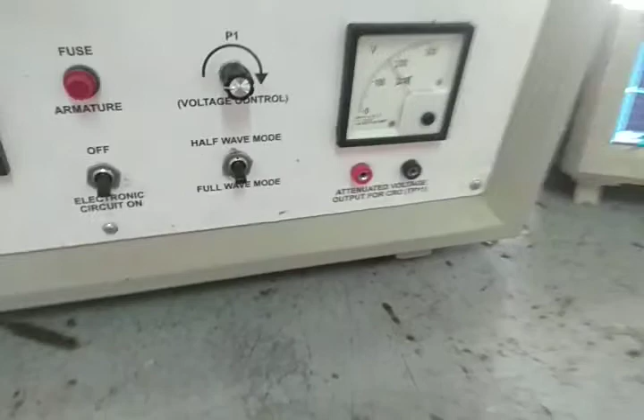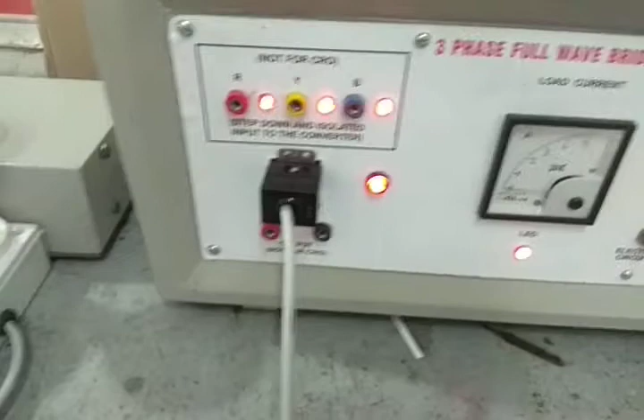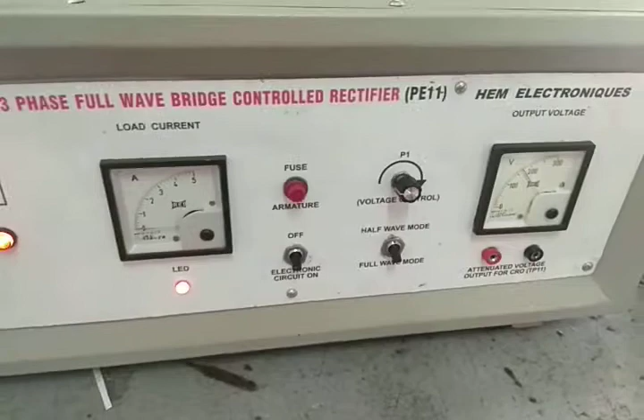Attenuation is already done, 10 times attenuation. These test points are directly high voltage test points. Of course they are isolated, but they are still high voltage. So you are not supposed to short any of these test points. If you short this, the transformers will be shorted, and in any case if you short this, the output will be shorted. So this is the main precaution any user has to take.